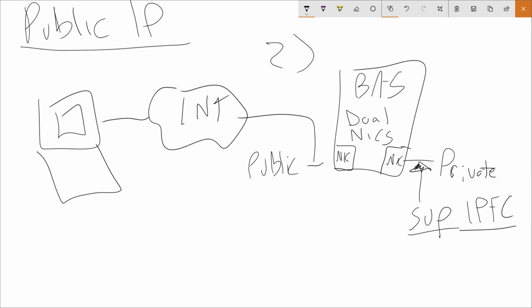But like I said, public IP is very much frowned upon, but it is something you can do. I often see this on new construction while the building's being built, and it's semi-acceptable then. You'll have someone who maybe puts in a 4G cellular device and connects the BAS to it so that you can have remote connectivity to the BAS server, do that remote commissioning, and then you disable that device after the project's complete. But this is frowned upon.